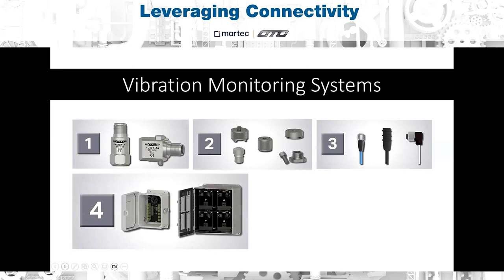The fourth component of a vibration monitoring system is the enclosure. Enclosures and junction boxes are mounted locally to the machine and can be used to take measurements from multiple sensors in one central location. You don't always necessarily need to utilize a junction box, as you can just run the signal directly from the sensor back to your monitoring system. However, having that option to take manual readings local to the machine can also be helpful.